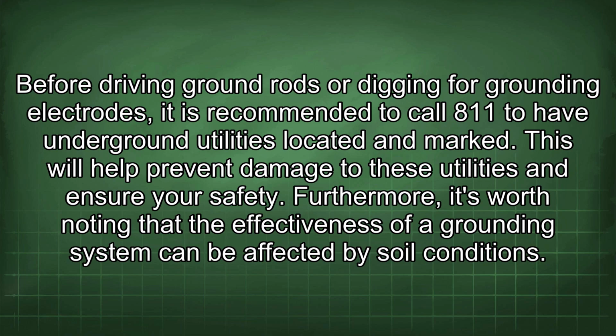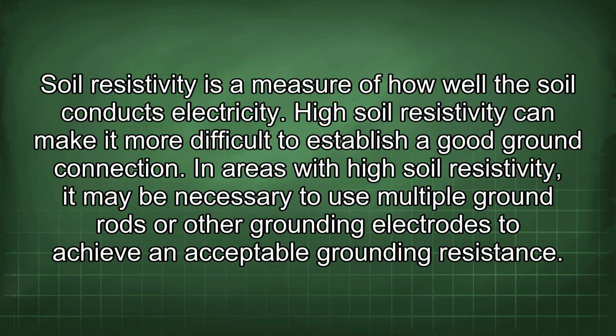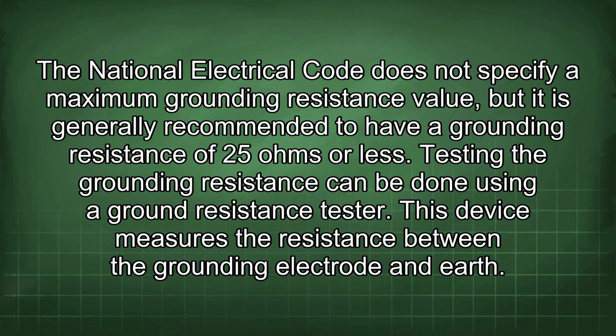Furthermore, it's worth noting that the effectiveness of a grounding system can be affected by soil conditions. Soil resistivity is a measure of how well the soil conducts electricity. High soil resistivity can make it more difficult to establish a good ground connection. In areas with high soil resistivity, it may be necessary to use multiple ground rods or other grounding electrodes to achieve an acceptable grounding resistance. The National Electrical Code does not specify a maximum grounding resistance value, but it is generally recommended to have a grounding resistance of 25 ohms or less.